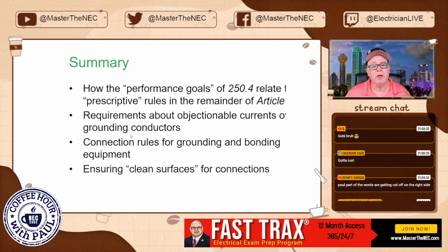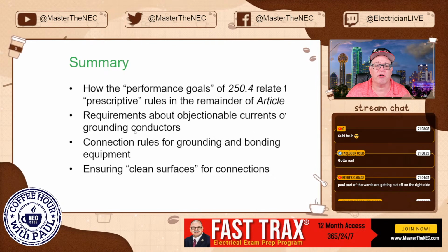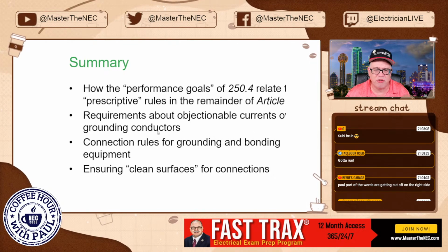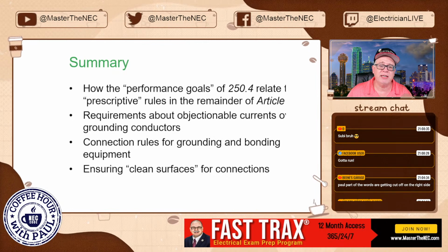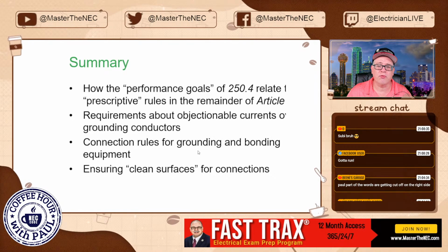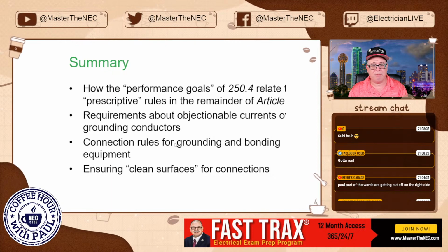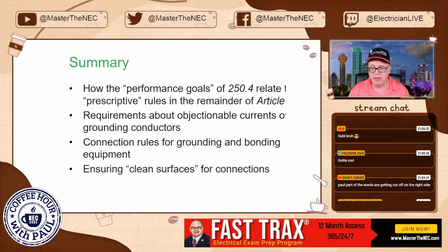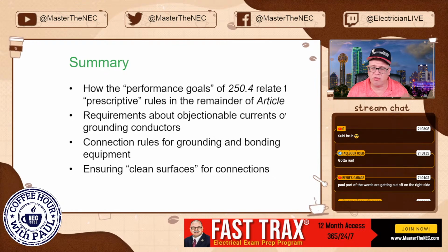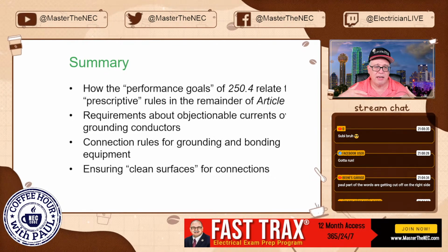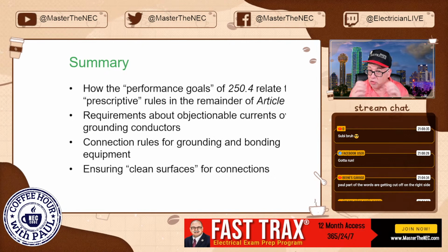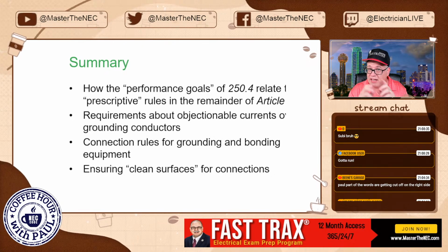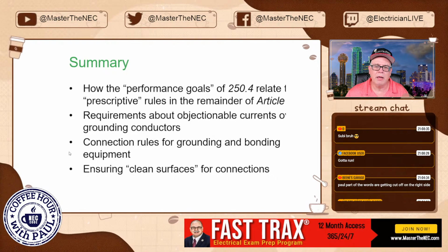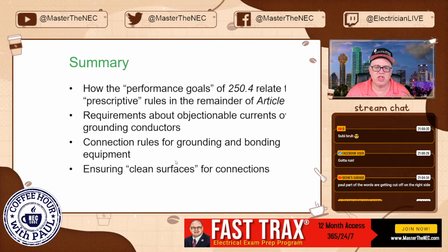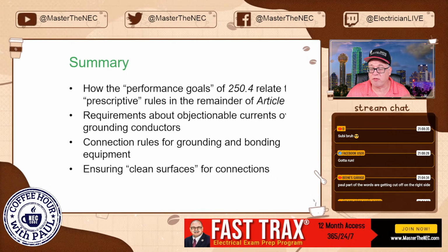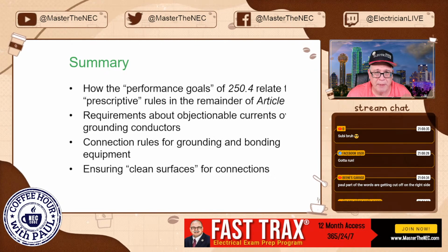All right, number 2, requirements about objectionable currents over grounding conductors. We went extensively over that. You should know that now. Number 3, connection rules for grounding and bonding equipment. We talked about the different types, the eight types of connections you can make, the importance of those connections. We even talked about low impedance, effective ground fault current path and why that's important. And those connections are vital to that taking place as well. And then lastly, we talked about ensuring clean surfaces for all connections, especially where anything looks suspect.